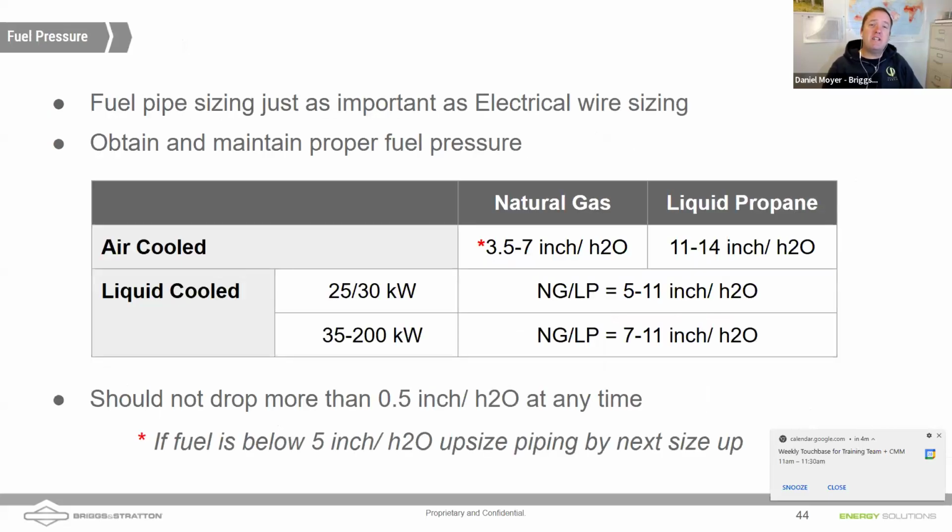Fuel sizing, Andy runs a bunch of trainings as well, and we'll have opportunities to do that. I would say, Andy, if you're still listening, undersized fuel lines is probably one of the biggest problems that a lot of times these are running into. So understand that there's not a lot of pressure in some of these gas lines, and if you are going to be doing these, we have tools to help you size some of those fuel lines.